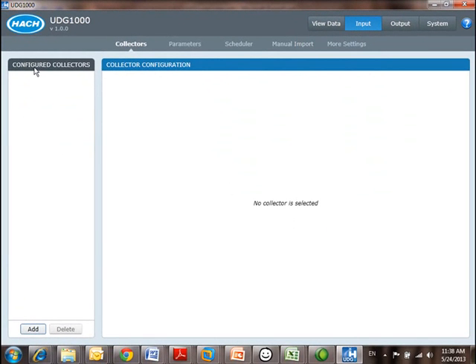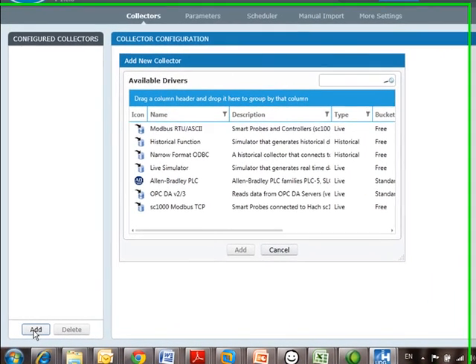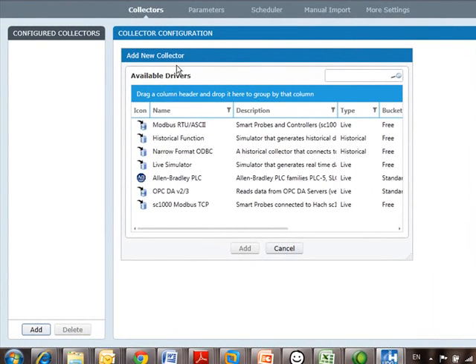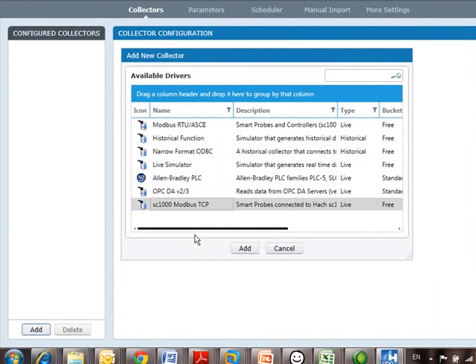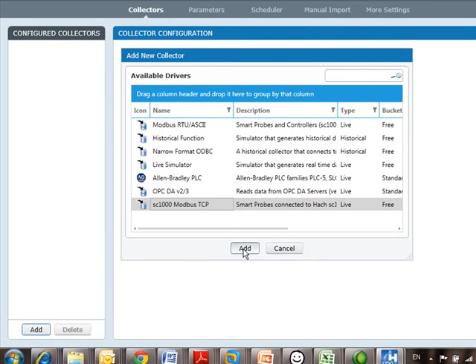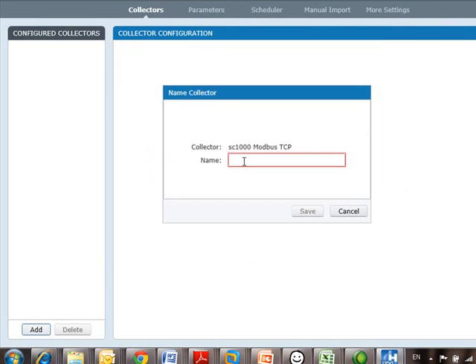Here are my configured collectors. I don't have any, so I'm going to add a collector in. Here are the available drivers, so these are the things I can communicate to. I want to connect to an SC1000, and I'm going to connect to it and communicate to it via Modbus TCP. So this is SC1000 that's on my local area network here, and it's IP addressable. So I go ahead and click Add.